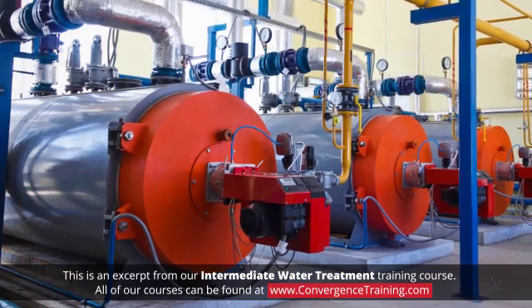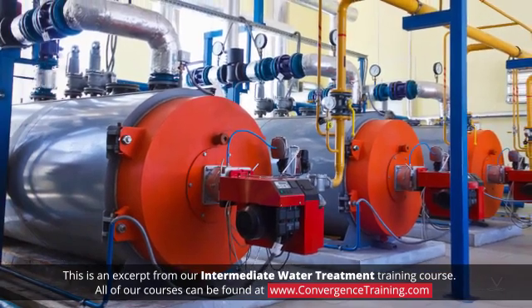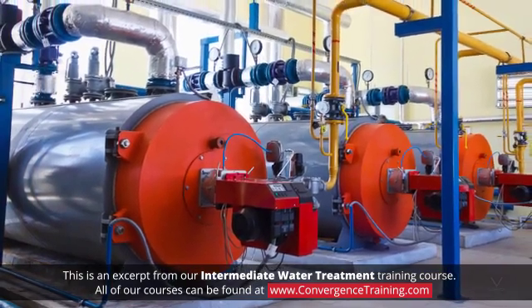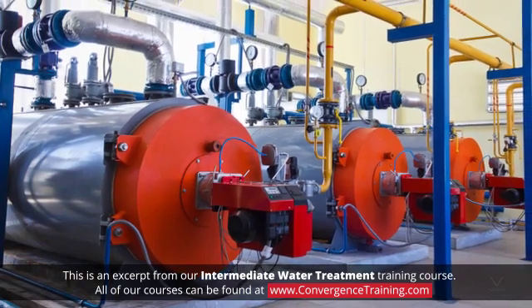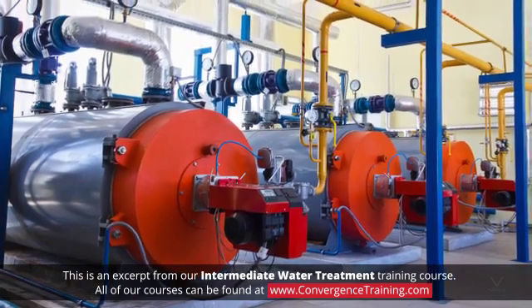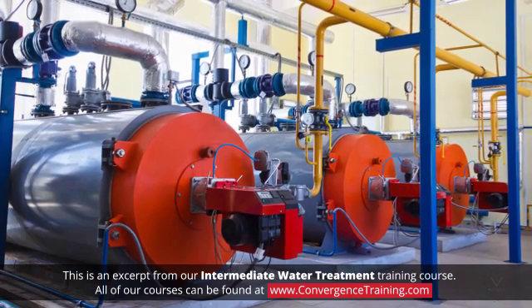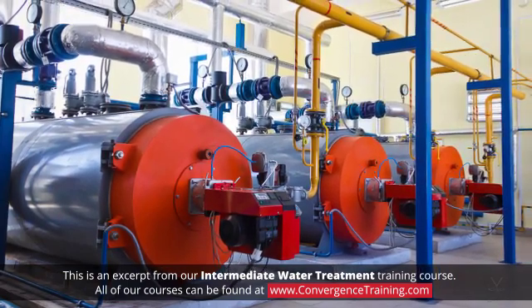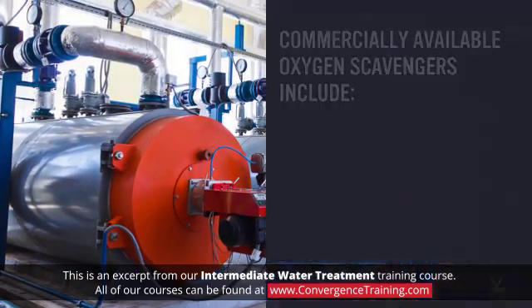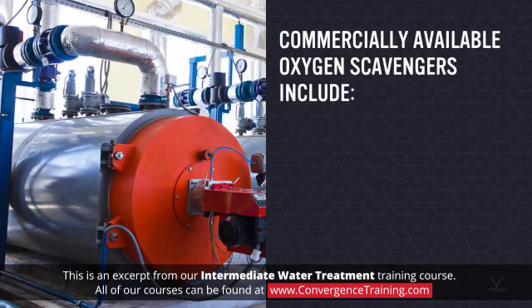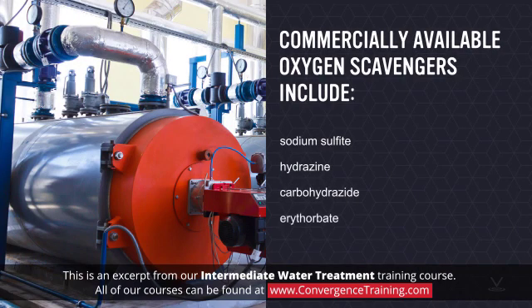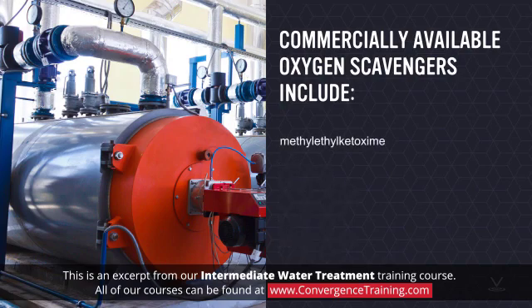Considering the corrosive potential of oxygen, it is best to remove all traces of oxygen from boiler feed water. This can be done by adding chemical oxygen scavengers that react with free oxygen in the water to form harmless oxidized products.